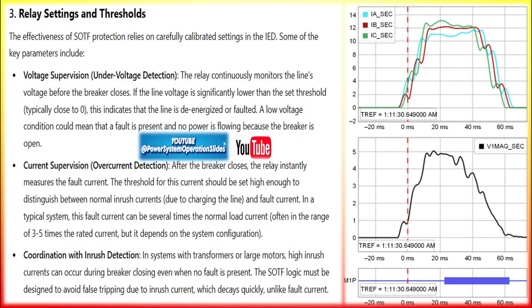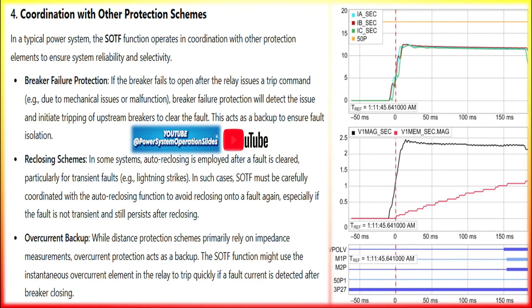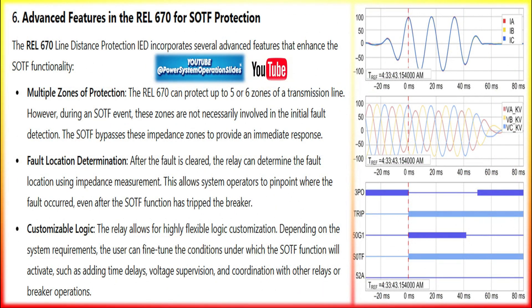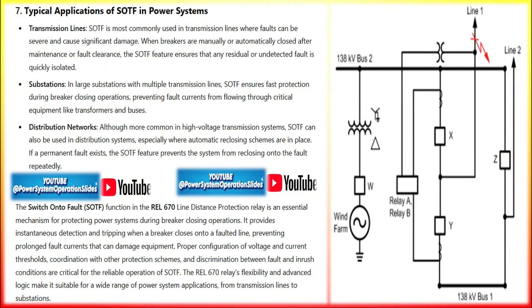The SOTF function typically activates under these conditions. When the breaker closes onto a fault, there will be a sudden increase in fault current. Before the breaker closes, the voltage across the line is usually low — zero or near zero if there is a fault. The relay monitors the line voltage and senses that there is no healthy voltage present before closing the breaker. As soon as the breaker closes, if the current rises sharply — indicative of a fault — the SOTF function is triggered. The REL670 Line Distance Protection IED is designed with advanced features for fault detection, including SOTF.